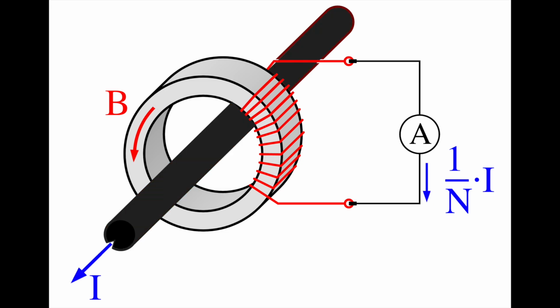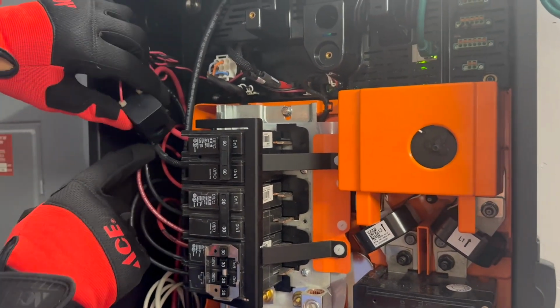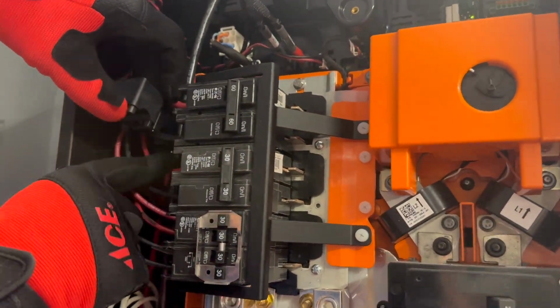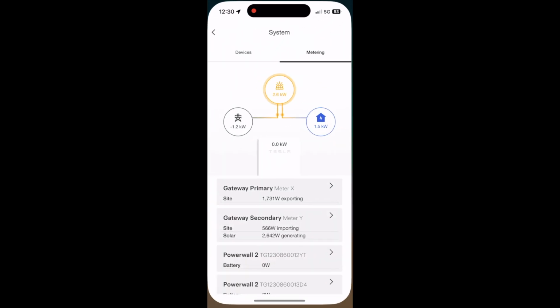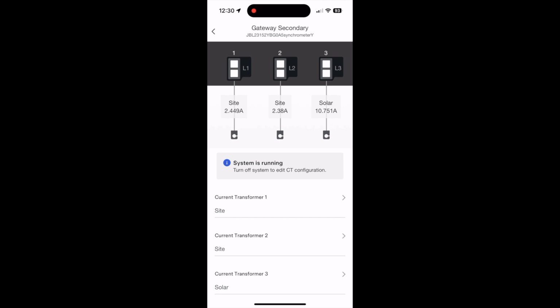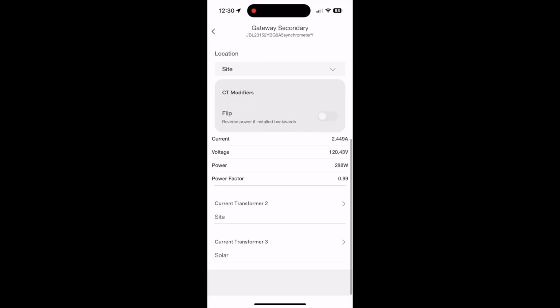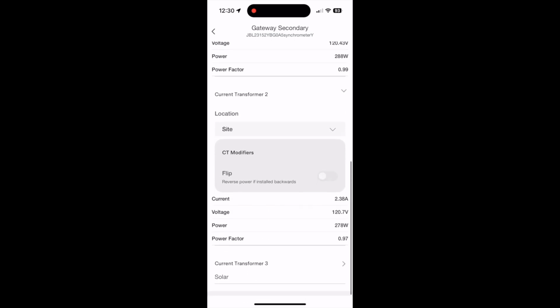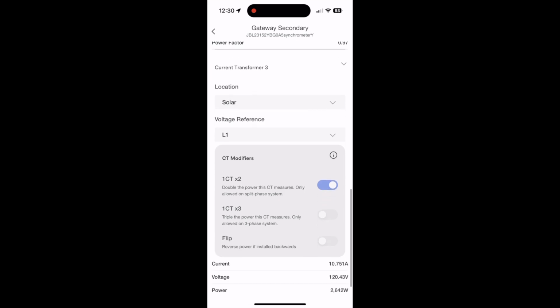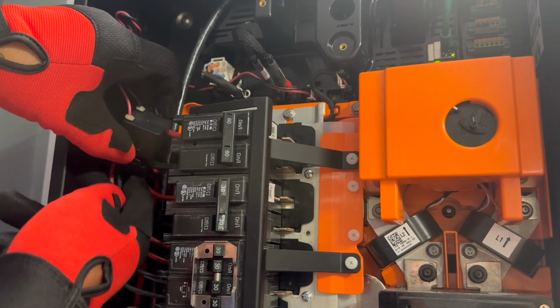So I tried moving the CT to the other phase. This would be a great time to mention that physically changing this to the other phase is totally unnecessary because of the Tesla One app. The Tesla One app is intended for installers but is available to everyone, and you can log in via your normal Tesla account username and password, at least as of 2024. First, notice that for all the CTs, 1, 2, and 3, you can just flip them in software. So if that's your issue, it's a software fix. As for me, the critical feature it has for what I'm doing here is that you can configure CT3 to say which line or phase, L1 or L2, the CT is measuring with respect to. Rather than moving it from one phase to the other physically, you can just select in the app that actually, this is measuring with respect to L2, not L1, or vice versa. Much less electrocution-y. But I didn't know that yet, so here's the hard way.